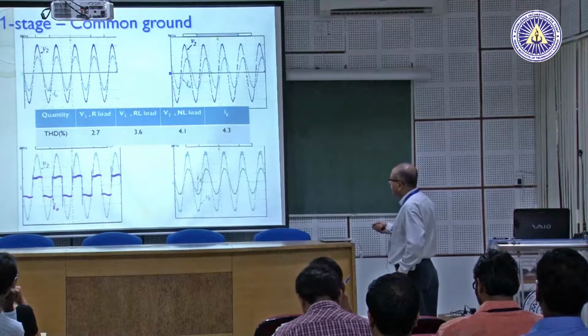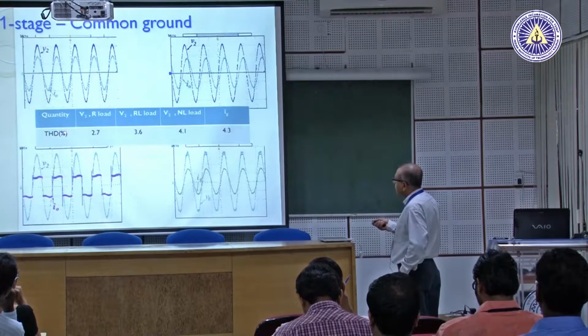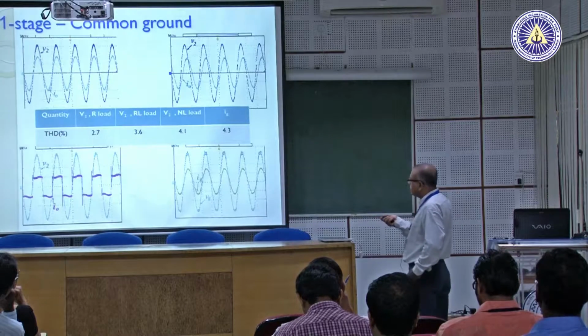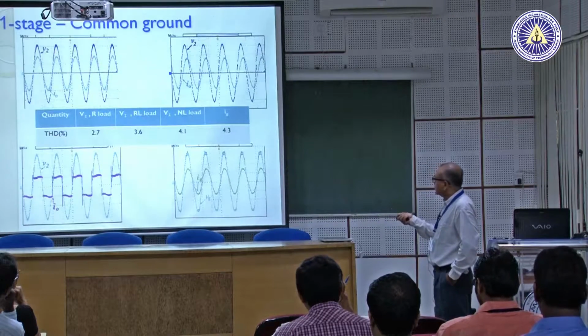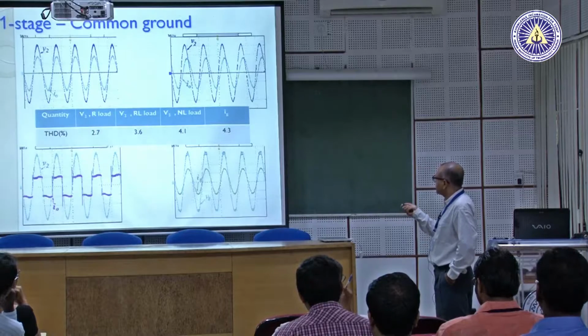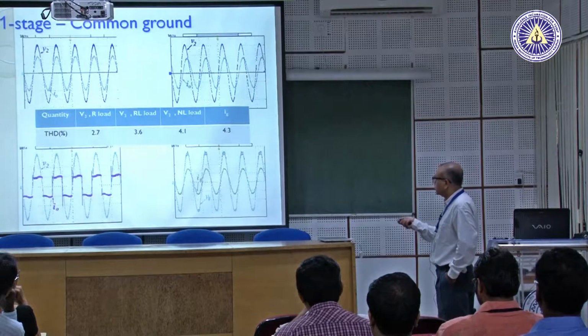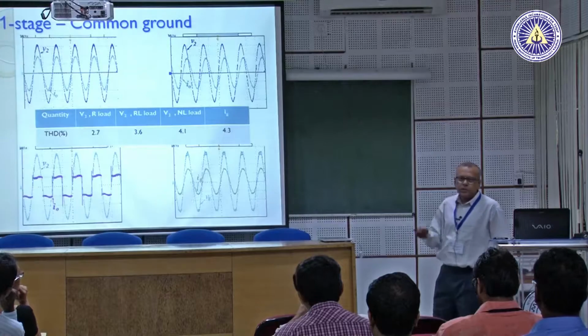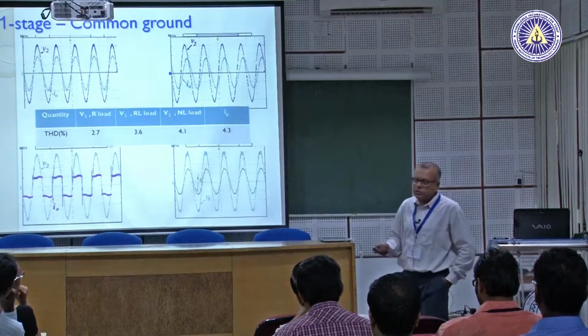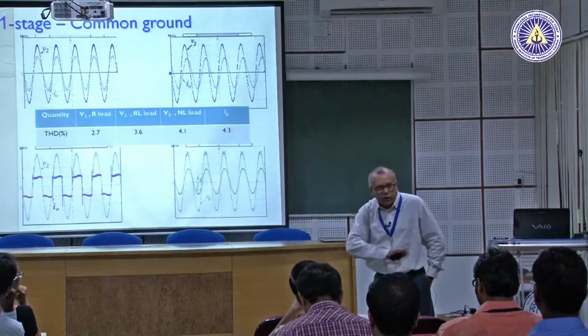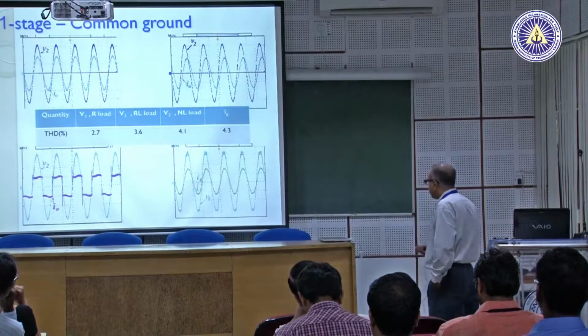That is completely in the open domain, and the voltage THDs are 2.7% in the first case, 3.6% in the second case, and 4.1% in the third case. The limit is 8% as per the IEEE standard, so that is well within the limits.